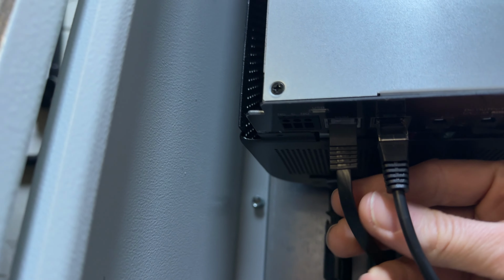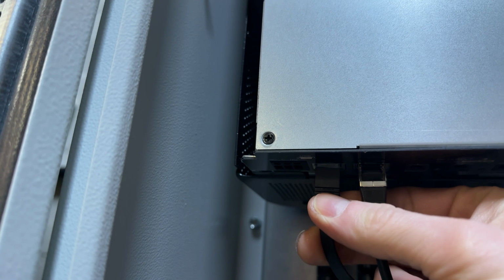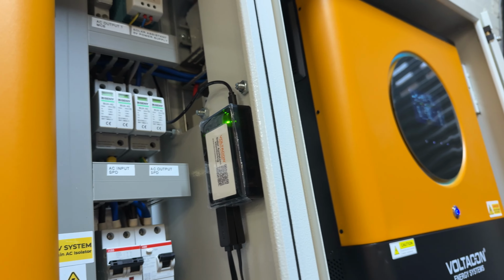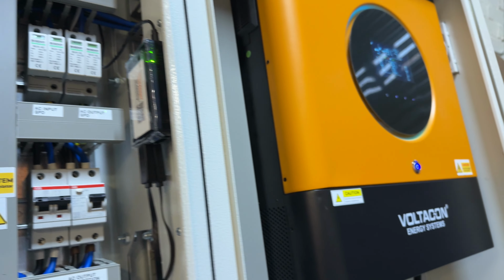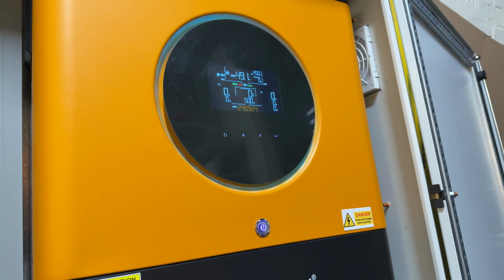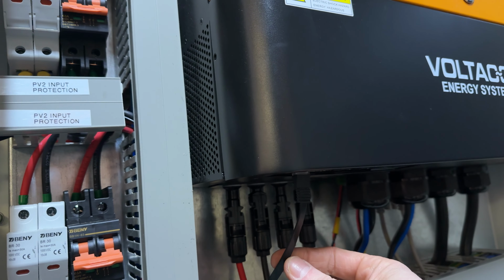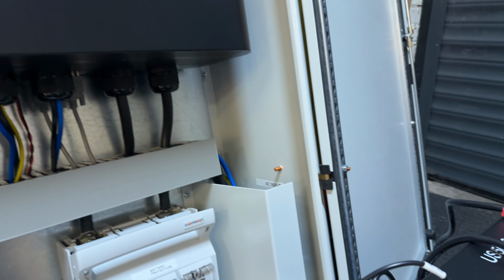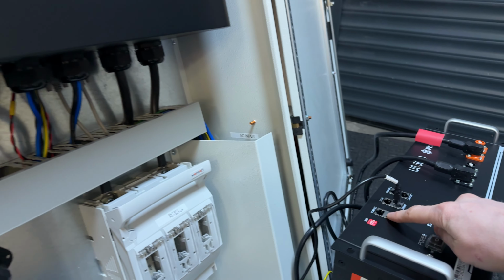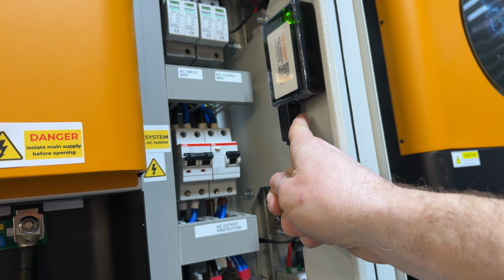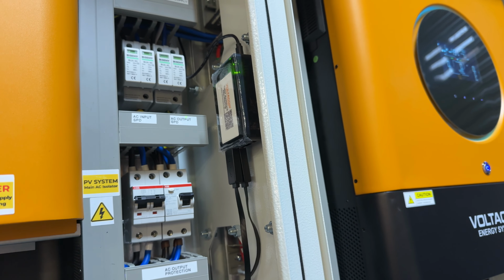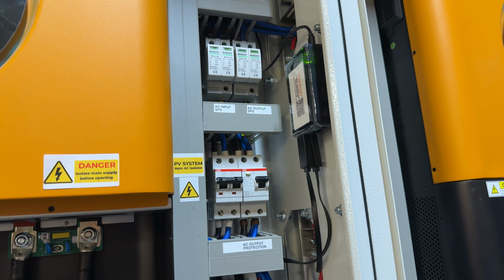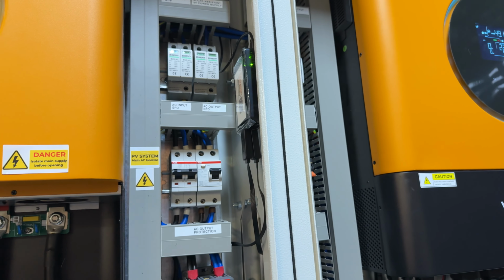This is the control port for the battery. That's the one. This port is called the communication port, and we feed the data to the Solar Assistant controller. So this inverter is feeding data to the Solar Assistant, and the secondary inverter is also feeding data to the Solar Assistant controller. So that's the cable. You may also get a console cable connected back to the Solar Assistant. There is a spare USB port, and that means the controller here will monitor the data of all your devices, the batteries and the inverters.